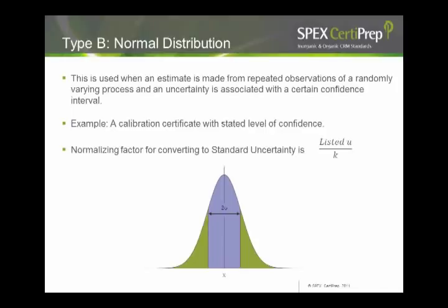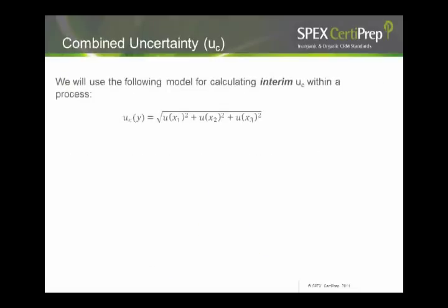Once you know these components, you should quantify the uncertainty from each of these within the process. Now, the information obtained in step 4 will consist of a number of quantified contributions to overall uncertainty, whether they are associated with the individual sources or with the combined effects of several sources. This contribution is expressed as standard deviation and should be combined according to appropriate rules to give combined standard uncertainty. Once you have an idea about the combined standard uncertainty for the overall process, you would expand it by applying an appropriate coverage factor.